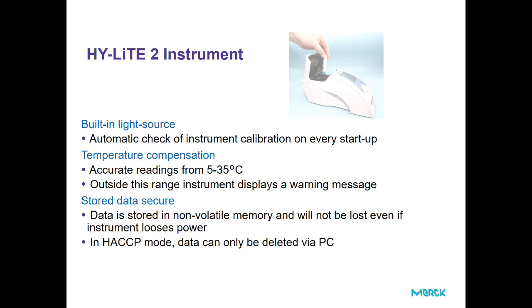The second benefit is temperature compensation. The bioluminescent reaction depends on the temperature. It means different temperatures give different kinetics of the reaction and different results. The HY-LiTE luminometer automatically compensates the result within the temperature range from 5 to 35 degrees. And when outside of this range, the instrument gives you a warning message.